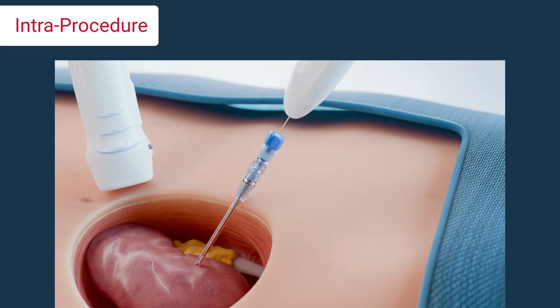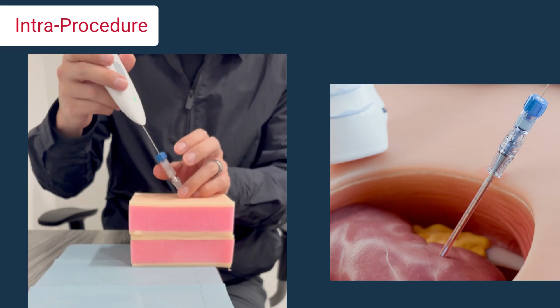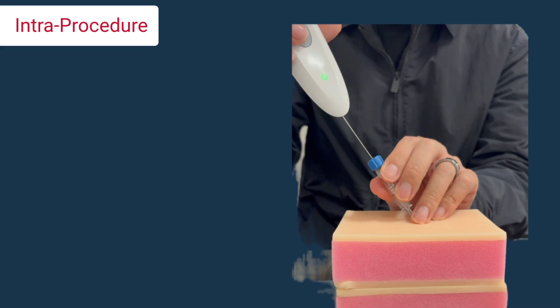Here is a tip for optimal success. Using your free fingers, usually the index finger and thumb, screw the depth gauge onto the guide needle or needle shaft. Stabilize your hands by placing the fourth and fifth fingers on the patient's skin while keeping your index finger and thumb on the depth gauge or guide needle. This hand position maximizes control and allows for withdrawal of the entire system as one unit.